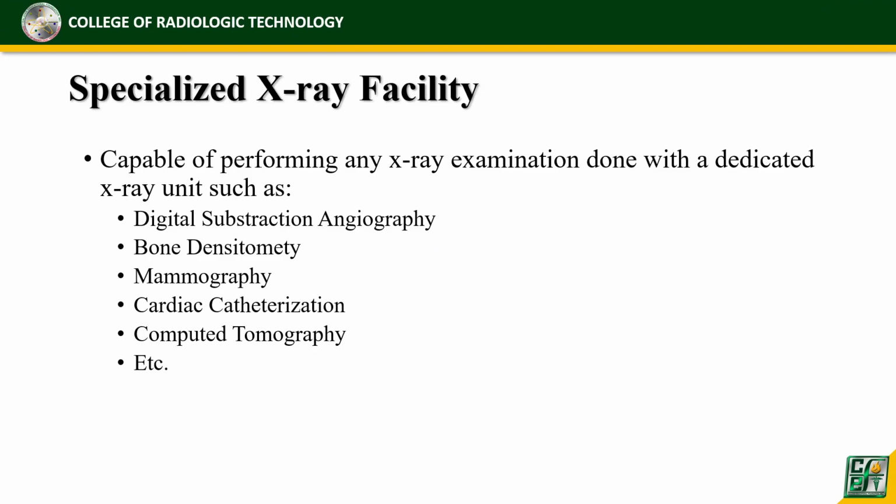And then, we proceed to the specialized X-ray facility. So dito ay ang binibigyan lang ng specialized X-ray permit ay yung mga machine or yung mga institution na may mga dedicated X-ray unit. When we say dedicated X-ray unit, okay, so kasama dito yung mammography. Mammography is dedicated only for the radiographic examination of the breast. Okay, bone densitometry is dedicated only for bone densitometry. Hindi siya pwedeng gamitin sa general radiography. Diba? Okay?